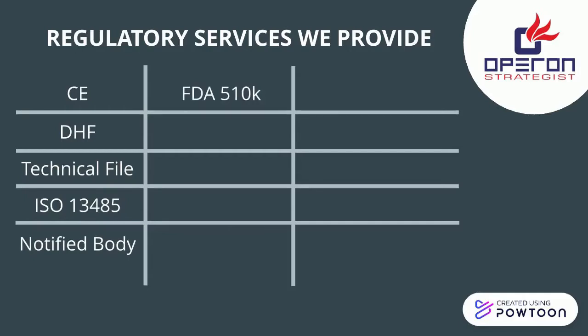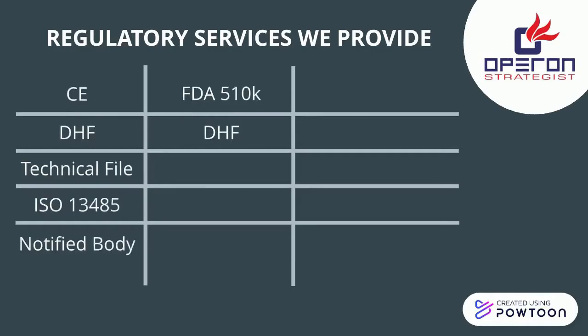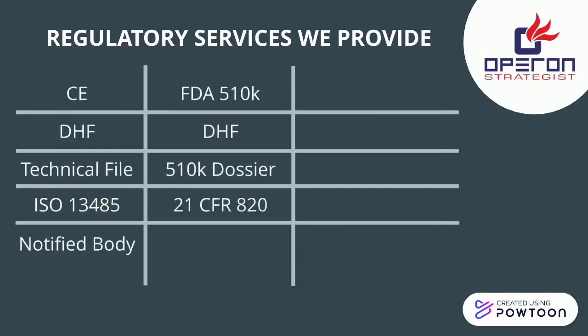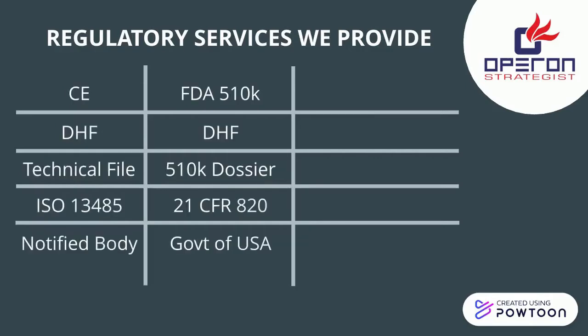FDA 510K. To acquire US FDA 510K, the manufacturer must document the product quality, safety and performance under the 510K dossier. The preliminary requirement is the design history file DHF. 510K dossier. This creates a groundwork for the creation of 510K dossier, as we have done with the CE marking technical file. From the facility point of view, 21 CFR Part 820. 21 CFR Part 820 is a mandatory requirement for quality management system. Government of USA. Submission of all the files are done to the Government of USA via online portal. US FDA then audits the complete applications and provides us with 510K clearance. In US FDA, the manufacturing facility is audited after the 510K within a stipulated time period.